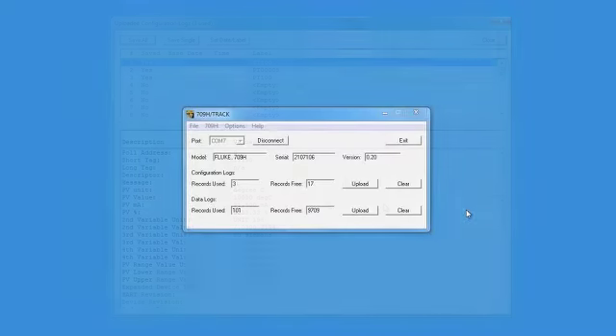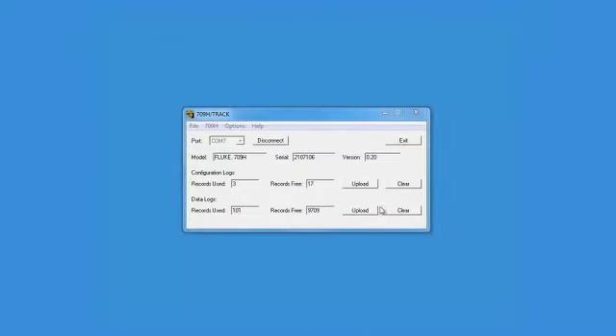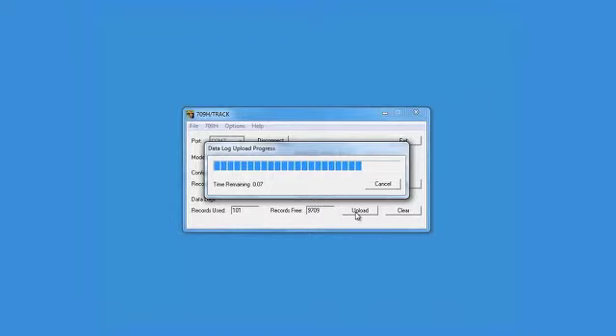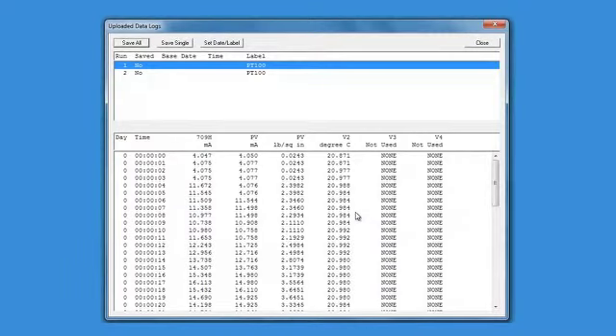Upload Logged Milliamp Measurements and HART PV Data. Select the Data Logs Upload button to retrieve the saved HART data logged in the 709H. The 709H can store up to 9,800 records and 99 individual sessions.